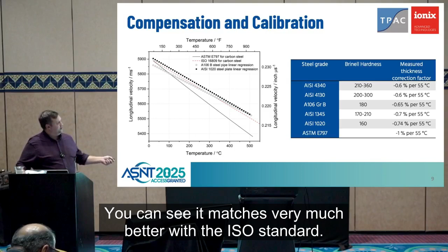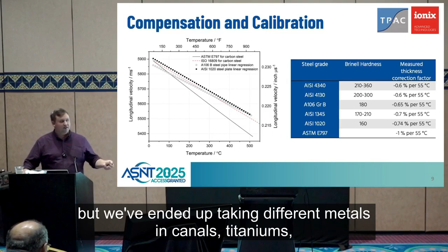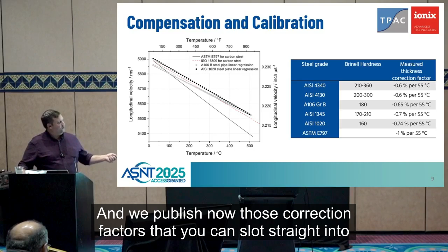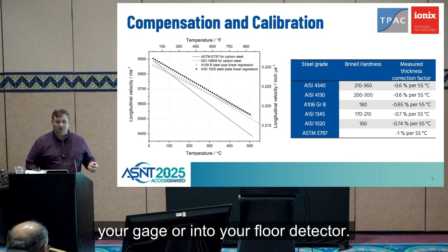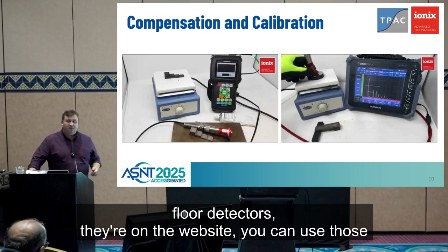We've taken some actual measurements of steel here. You can see it matches very much better with the ISO standard, but we've ended up taking different metals, Inconels, titaniums, steels, stainless steels, and we publish now those correction factors that you can slot straight into your gauge or into your flaw detector. If you want some more information on those, there's some nice videos of that with standard commercial gauges, flaw detectors. They're on the website. You can use those to have a look, and then how we use those tables more effectively. But I don't want to go through all of those just now.